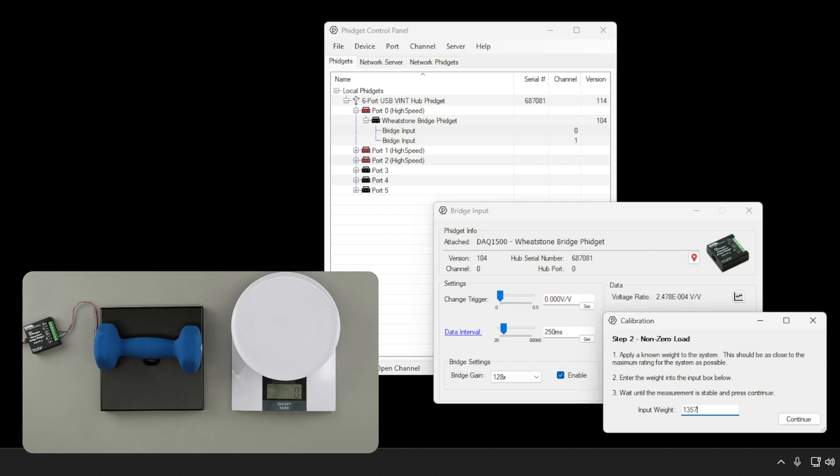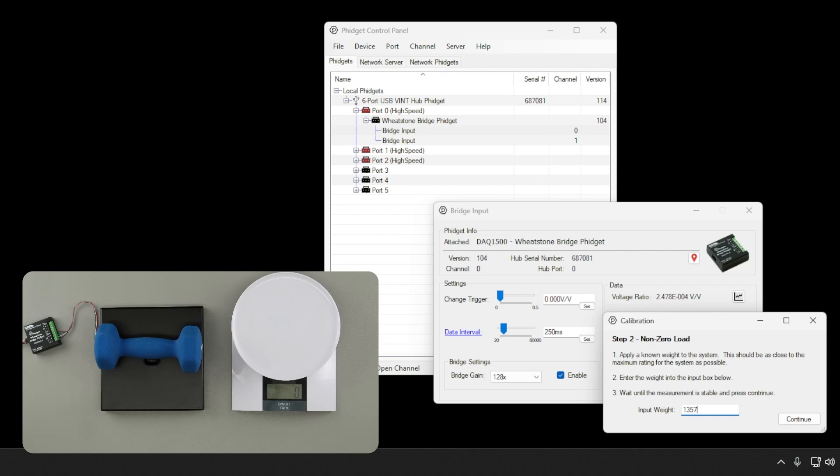The closer your calibration weight is to your system capacity, the more accurate your results will be. Here, for example, we would have more accurate results with a 5 kg weight for our 5 kg system. When your measurement has stabilized, the Continue button will be available to press.